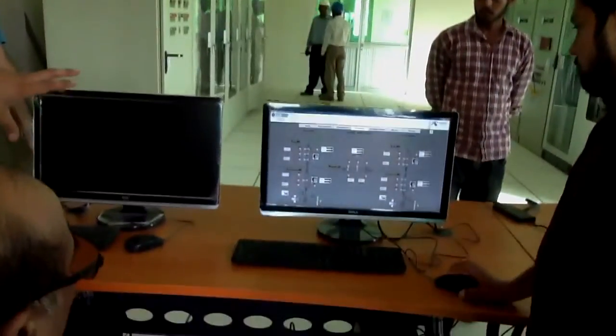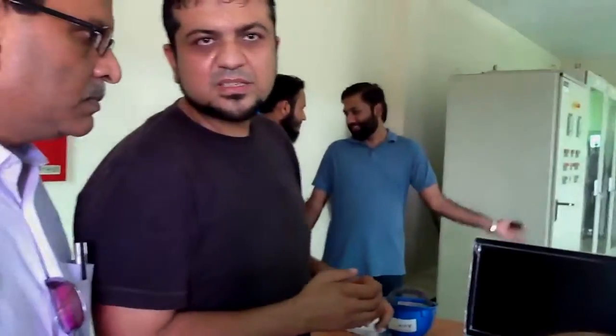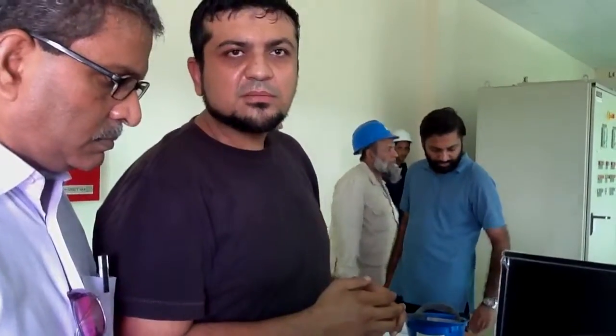This is our SCADA system, and all our 132 kV system, 22 kV system, shunt compensation system, and even the energy analyzer system, energy evacuation system, and metering system. All systems are connected through this SCADA. There are two parts of this SCADA. One is the operator workstation, and the second is the engineering workstation. Through the operator workstation, we can monitor the system and initiate commands, and through the engineering workstation, we can engineer our system to make some modifications.